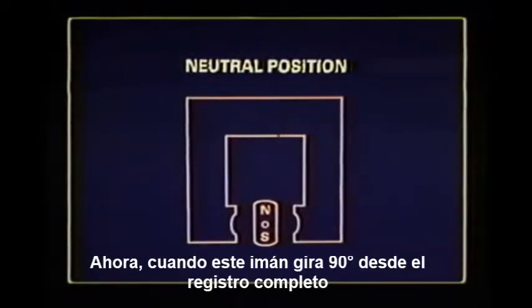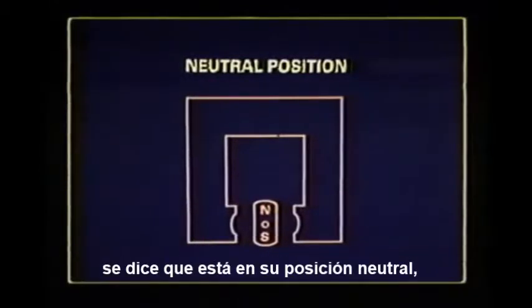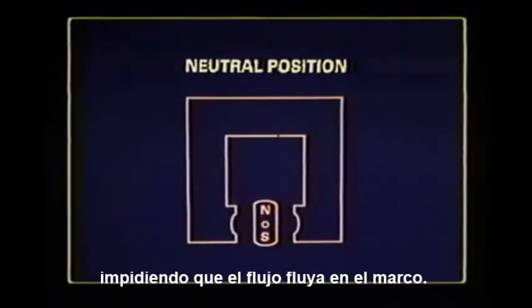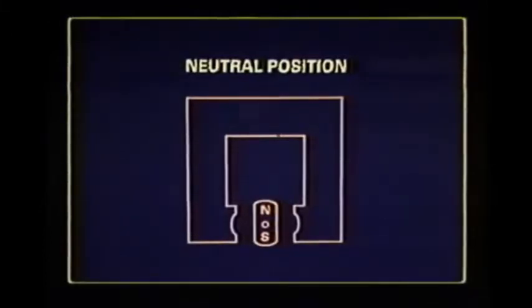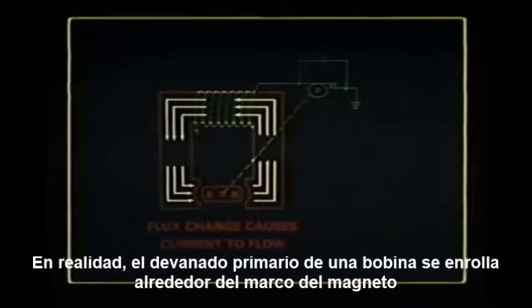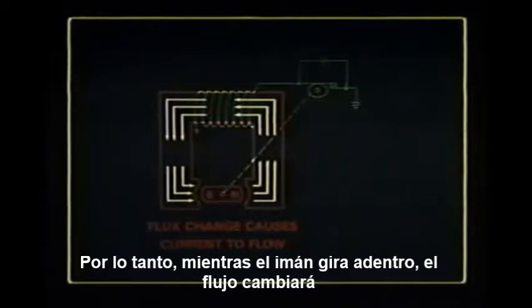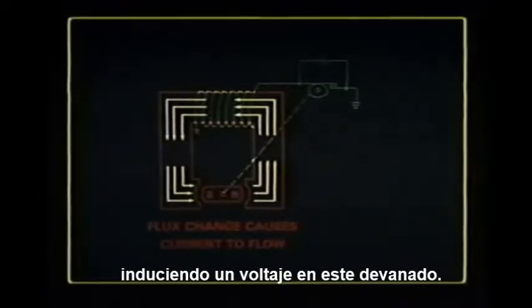Now, as this magnet rotates 90 degrees from full register, it is said to be in its neutral position, preventing the flux from flowing in the frame. The primary winding of a coil is actually wound around the magneto frame. So, as the magnet inside rotates, the flux will change, inducing a voltage into this winding. This causes the primary current to flow.